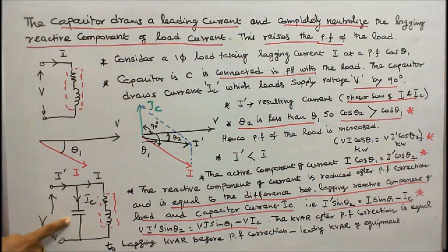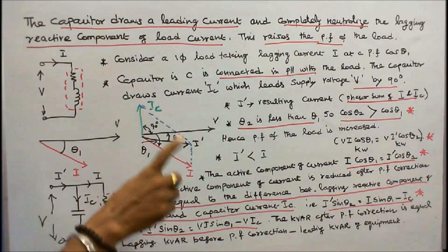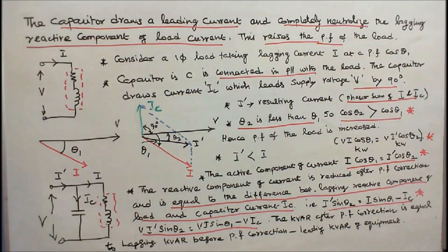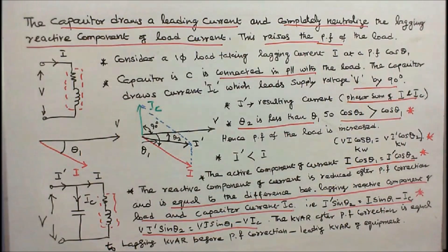Now capacitor C is connected in parallel with the load. The capacitor draws current Ic which leads the supply voltage by 90 degrees — it is an ideal capacitor. I dash is the resulting current, which is the phasor sum of I and Ic. Here theta 1 is the angle between V and I, and theta 2 is the angle between V and I dash. Since theta 2 is less than theta 1, cos theta 2 is greater than cos theta 1, so the power factor of the load is increased.